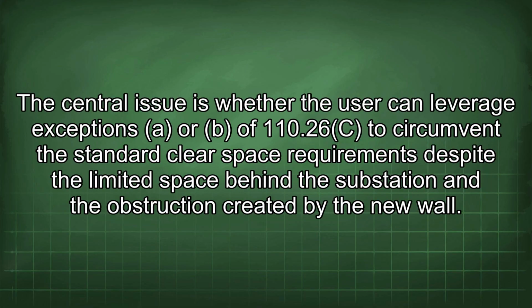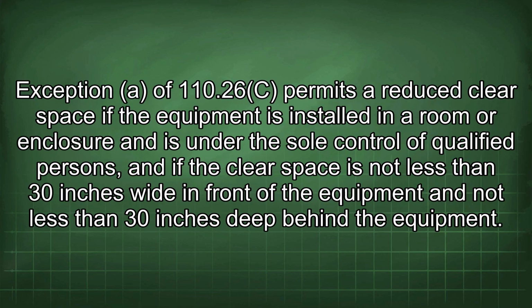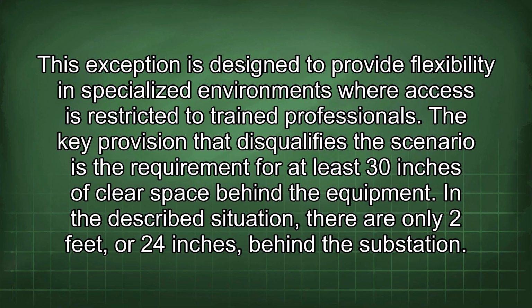The central issue is whether the user can leverage Exception A or B of 110.26(C) to circumvent the standard clear space requirements despite the limited space behind the substation and the obstruction created by the new wall. Exception A of 110.26(C) permits a reduced clear space if the equipment is installed in a room or enclosure under the sole control of qualified persons, and if the clear space is not less than 30 inches wide in front of the equipment and not less than 30 inches deep behind the equipment. This exception is designed to provide flexibility in specialized environments where access is restricted to trained professionals.